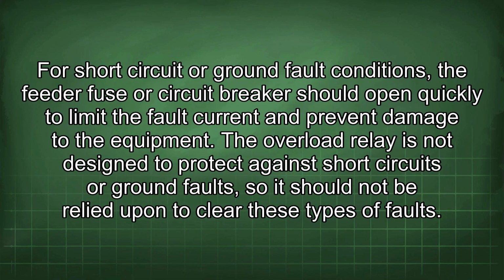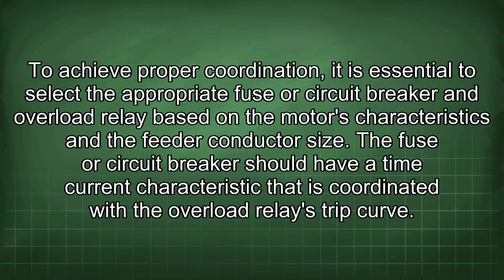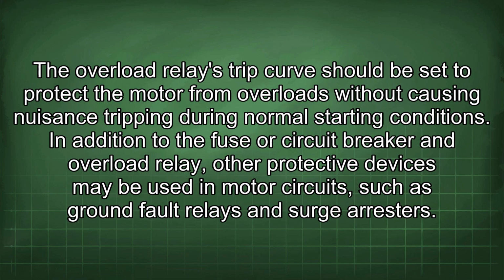For short circuit or ground fault conditions, the feeder fuse or circuit breaker should open quickly to limit the fault current and prevent damage to the equipment. The overload relay is not designed to protect against short circuits or ground faults, so it should not be relied upon to clear these types of faults. To achieve proper coordination, it is essential to select the appropriate fuse or circuit breaker and overload relay based on the motor's characteristics and the feeder conductor size. The fuse or circuit breaker should have a time current characteristic that is coordinated with the overload relay's trip curve. The overload relay's trip curve should be set to protect the motor from overloads without causing nuisance tripping during normal starting conditions.